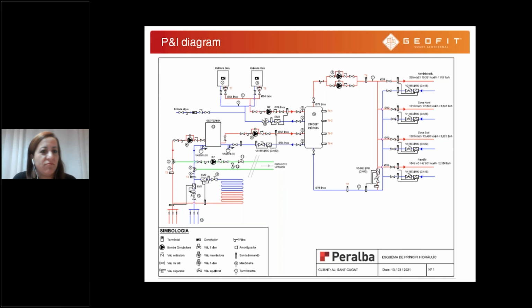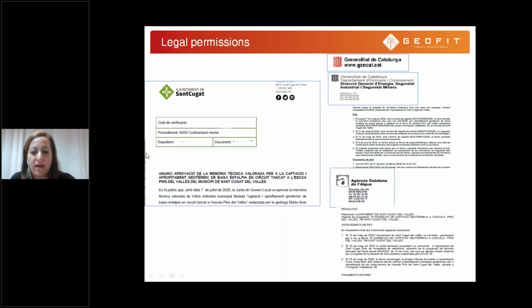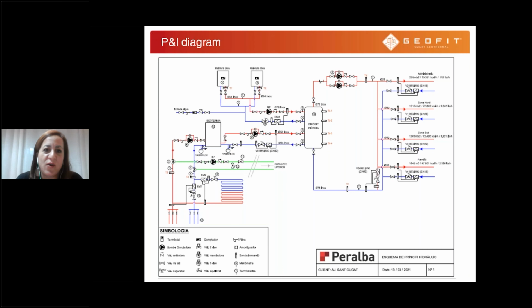After this, we clarify that we have all the instruments, all the things, and we do the piping and instrument diagram. This is the boreholes; we connect with the heat pump, and then connect to the tank, and this tank is also connected with the boilers. It exists in the building, and then goes to the school or the pavilion or another building. There is also another installation for passive cooling, which I will discuss later, but this is the final diagram that we have in Sant Cugat.